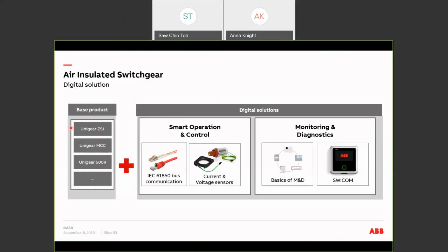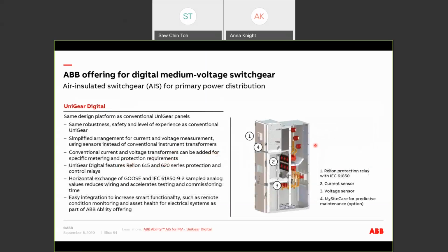Take air insulated switchgear, for example: we'll use the UniGear ZS1 platform, the UniGear ZS1 MCC or 500R. With this basic platform, we'll add in smart operation and control, as well as monitoring and diagnostics, making this switchgear smarter. So the digital panels will offer the same robustness and safety as the conventional UniGear panels. There are three main parts of the digital switchgear: the ABB protection relay with IEC 61850 communication, the current sensors, and the voltage sensors.